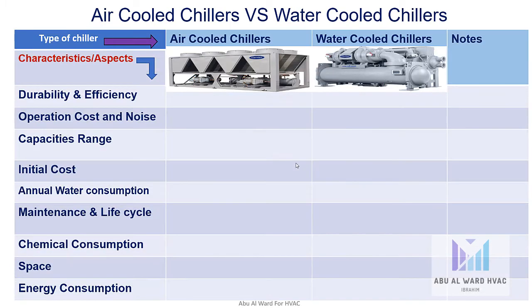We have many aspects. We need to see the differences between these two types according to those aspects. We have durability and efficiency. We know that air-cooled chillers are less efficient than water-cooled chillers, and that is because the air-cooled chillers depend on the dry bulb temperature for cooling the condenser, while the water-cooled chillers depend on wet bulb temperature, which is less than dry bulb temperature.